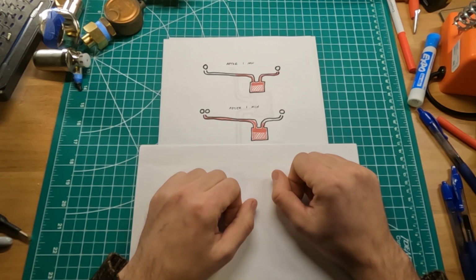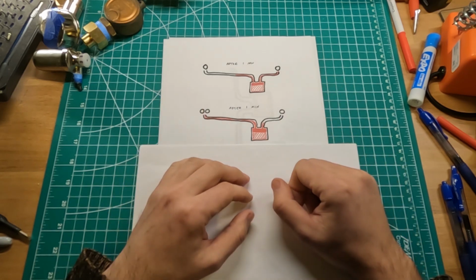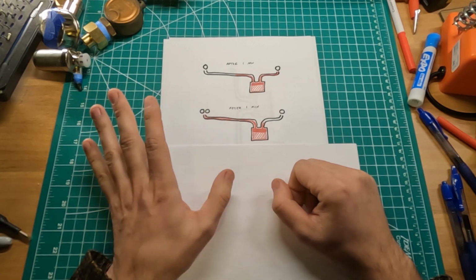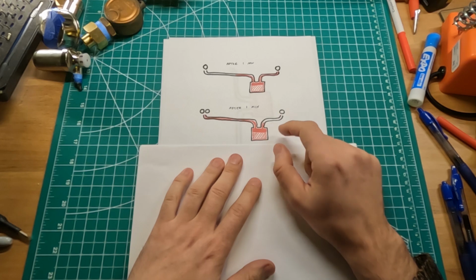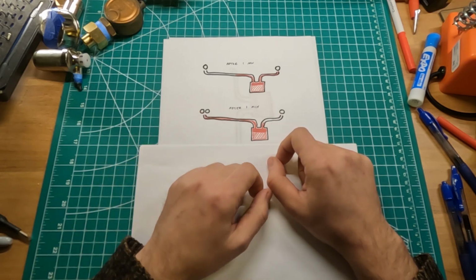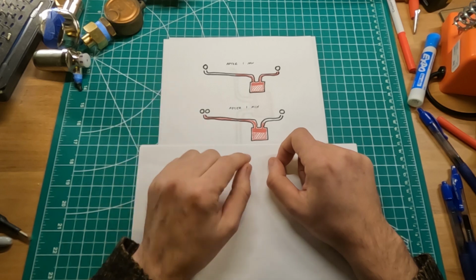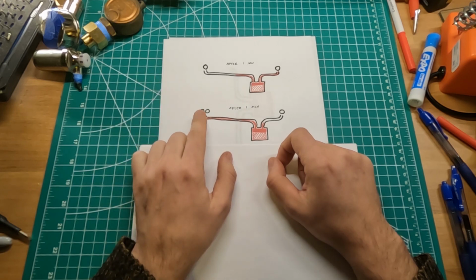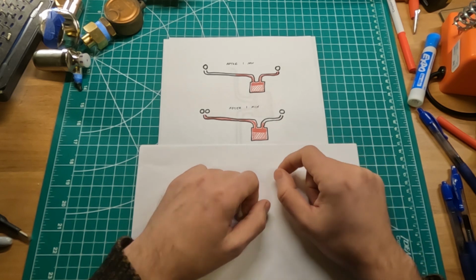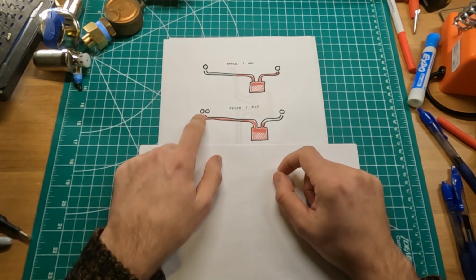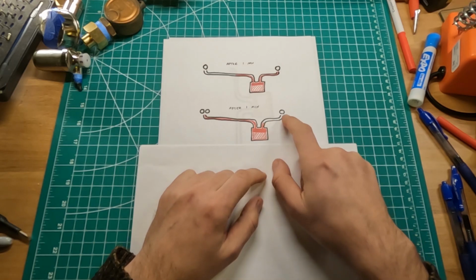So why, you might ask yourself, and the reason for this is because ultimately steam is quite lazy, and it wants to do as little work as possible. So as it's pushing out the air through the main vent on two sides, the bigger opening obviously implies that it's going to be easier to push out the air where we have a bigger opening than where we have a smaller opening, and because of that this pipe fills up with steam while this one just remains quite empty.